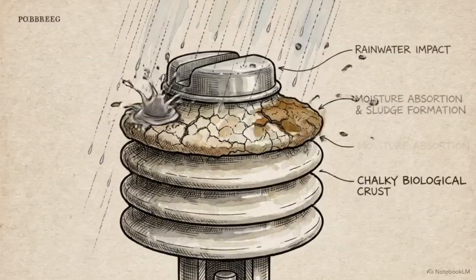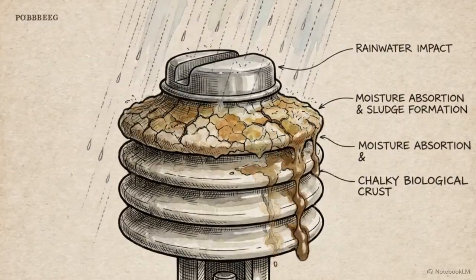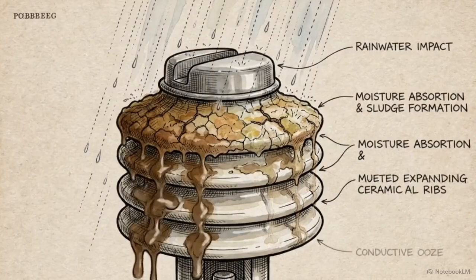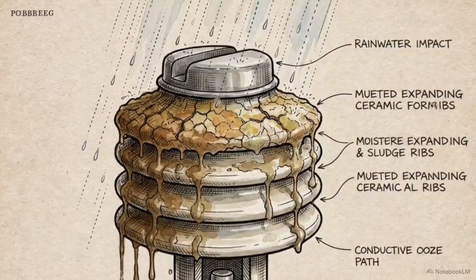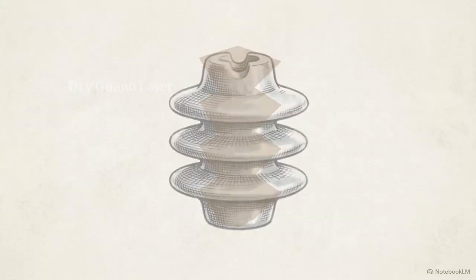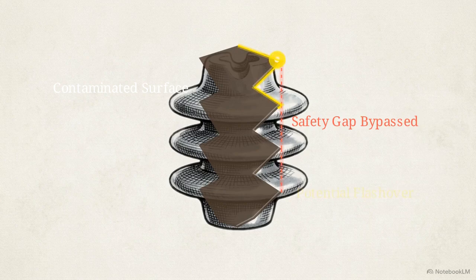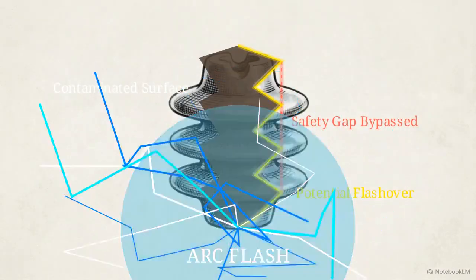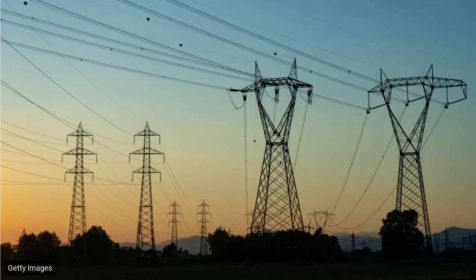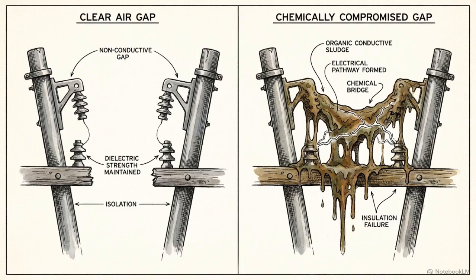When heavy fog or seasonal rain finally arrives, the water interacts with the uric acid, turning the dried guano into a chemically conductive liquid. This conductive sludge effectively shrinks the electrical resistance of the insulator. The current tracks right down the liquid layer, bypassing the safety distance entirely and triggering a massive arc flash. Even when grid engineers build gaps wide enough to avoid physical contact, the natural biology of the roosting birds chemically shrinks the safety margin until the system breaks.